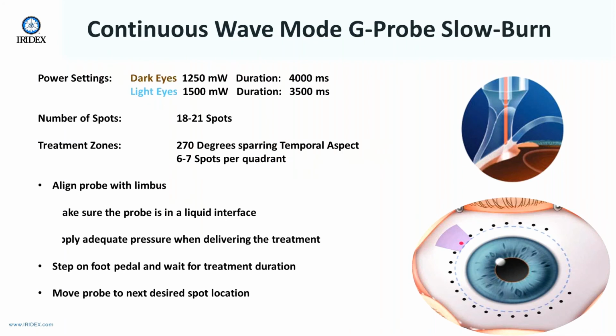For continuous wave mode slow burn, the power settings are a little bit lower. For dark eyes, 1250 milliwatts for a duration of 4000 milliseconds. For light eyes, 1500 milliwatts for a duration of 3500 milliseconds. Again, 18 to 21 spots, 270 degrees, sparing the temporal aspect. 6 to 7 spots per quadrant, and the technique is identical, tuning towards the pop and then backing off until you do not hear one.